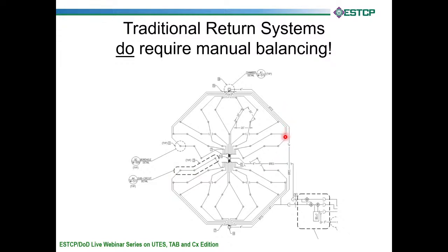Our next slide here shows a traditional GHX without reverse return, and this does require manual balancing. Nothing wrong with this design at all. It's a good way to do it. It actually gives you some access. Over here we have these vaults. We have a core vault, and in our core vault we have a bunch of isolation valves. We have two perimeter vaults where our balancing valves are.